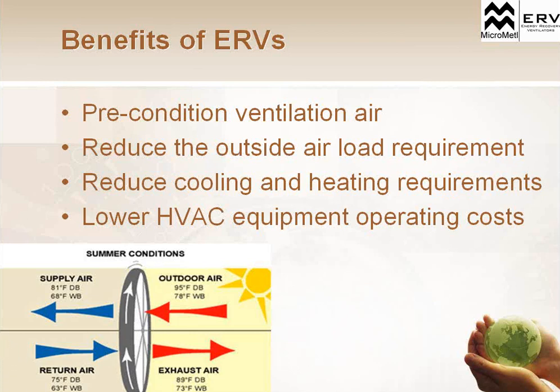On the top here, well, let's look at the bottom here. This is the building side on the left hand of this wheel. So we have exhaust air coming out of the building. And then at the top here, this would be fresh air coming into the building. Now, in a typical situation without that wheel, we would have a rooftop with an economizer. We'd be bringing in fresh air from that economizer through the supply air. We'd be sending exhaust air through some type of exhaust fan. With an energy recovery unit, we capture all the exhaust in the building. We take it through this energy recovery wheel.